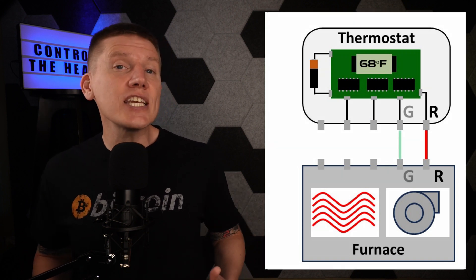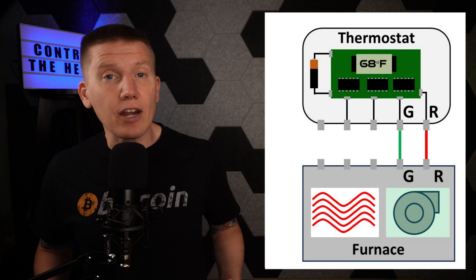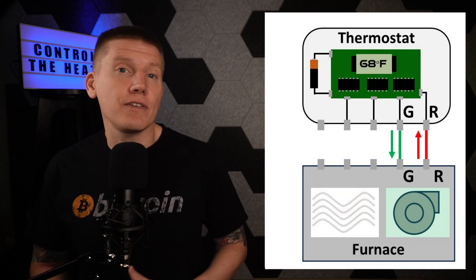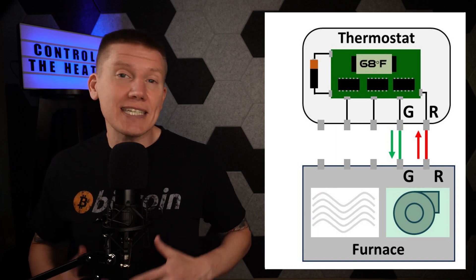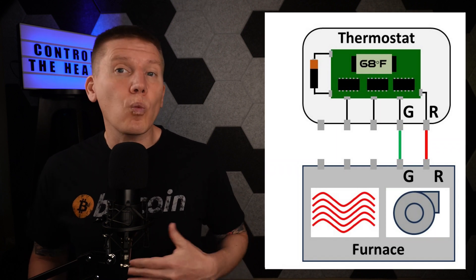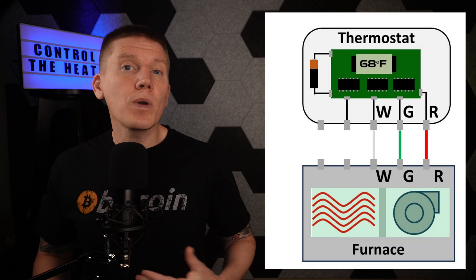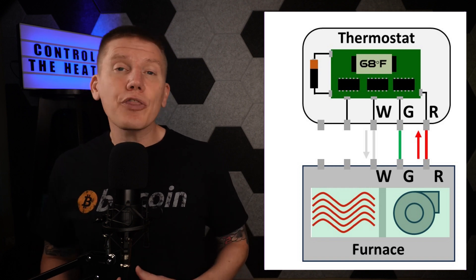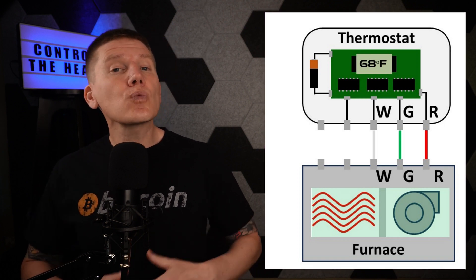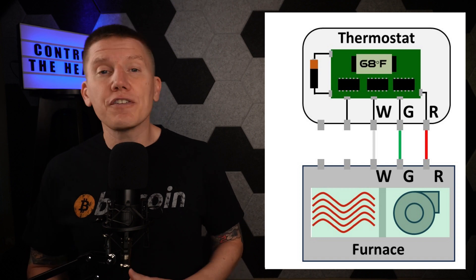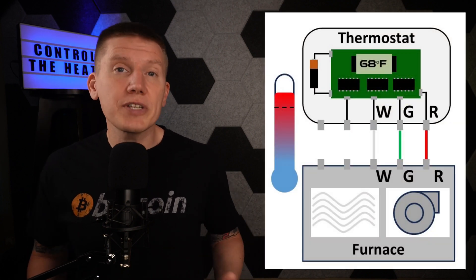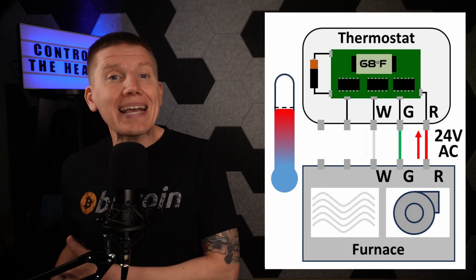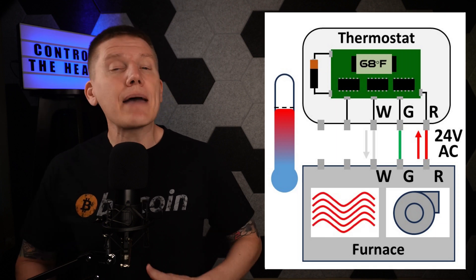The next wire is the G or green wire, which controls the fan in a forced-air furnace. When the thermostat sends 24 volts down the G wire, the furnace will power up the fan without turning on the heating part — running in fan-only mode. The W or white wire controls the heating part of the furnace. When power is sent down the W wire, the furnace goes through its startup sequence, turns the fan on when ready, and provides heat to the house. When the thermostat stops sending voltage down the W wire, the furnace stops providing heat, goes through its shutdown sequence, and turns the fan off. Under normal operation, when the room temperature drops below the set point, the thermostat sends 24 volts from the R wire back through the W wire, and the furnace starts up and blows heat around the house.